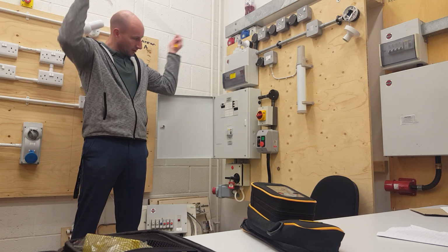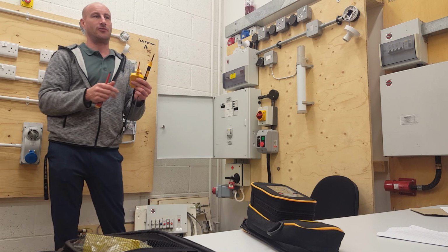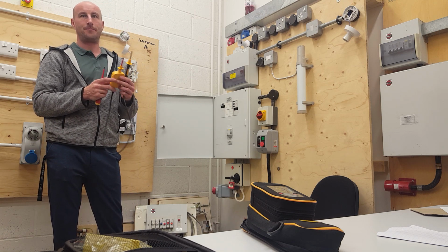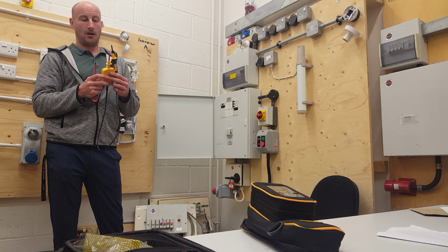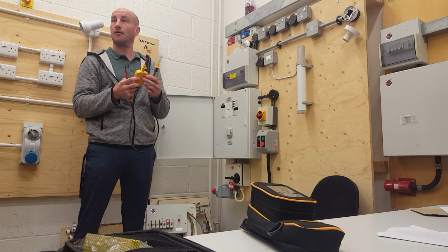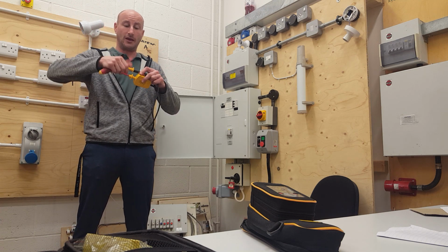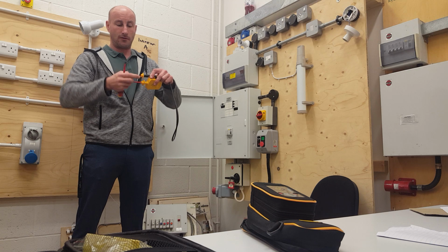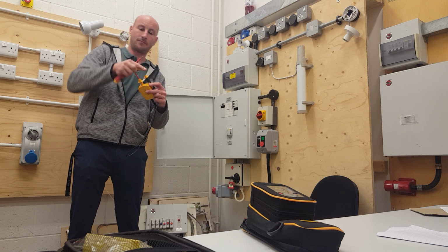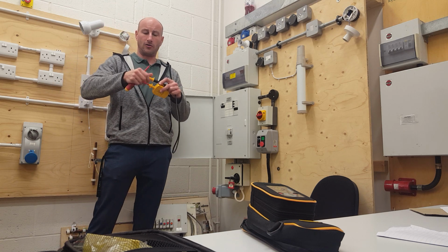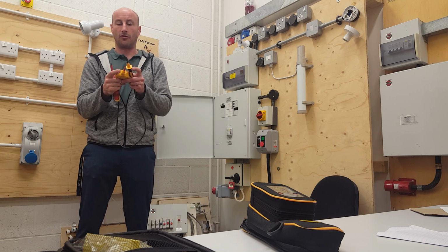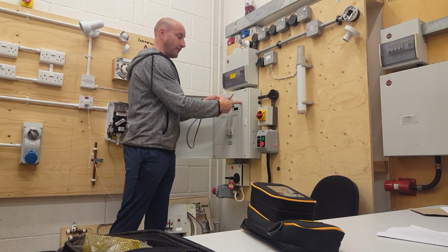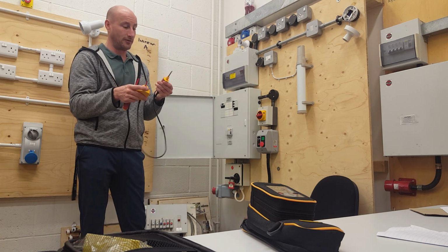And what has this tester got to have to comply with GS38? Got to have a safety standard sticker on it? Well, it's got to be British Standard. It's got to have a fuse inside. It's got to have fused test leads and finger guards. The reason it's got finger guards is so when you test on something, your fingers don't slide down and touch the live connections.